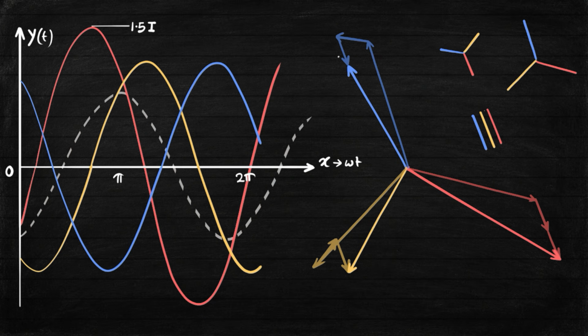But remember, this current is contributed by all three phases simultaneously. The direction of all three zero sequence currents is the same, and therefore, their instantaneous currents add together. So the neutral current is IN equals 3I0, where I0 is the zero sequence current of each phase. So the amplitude of the neutral current is 3 times the magnitude of the zero sequence current in one phase.